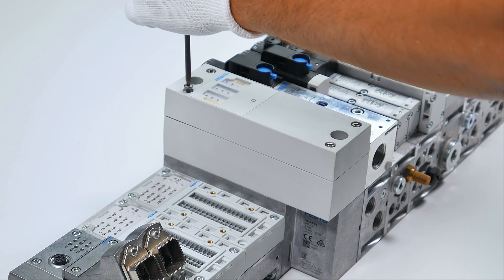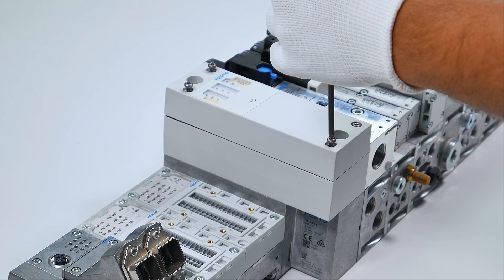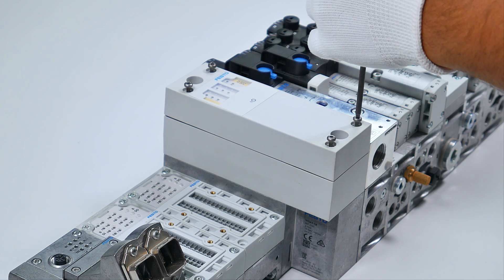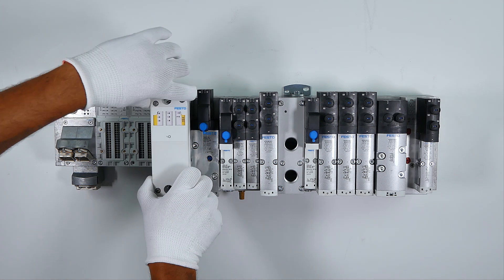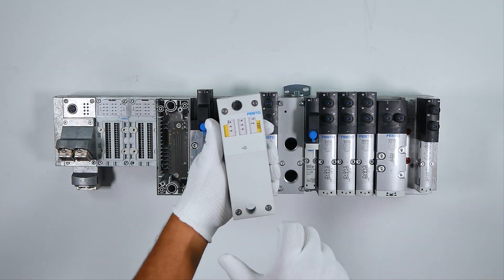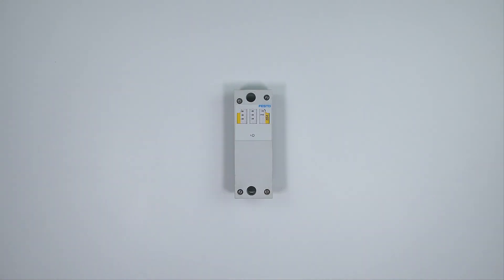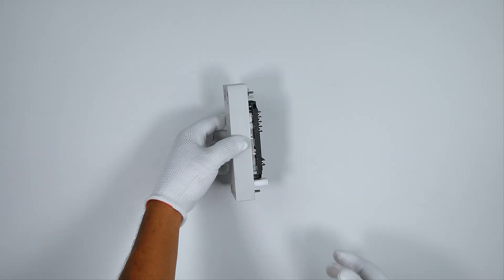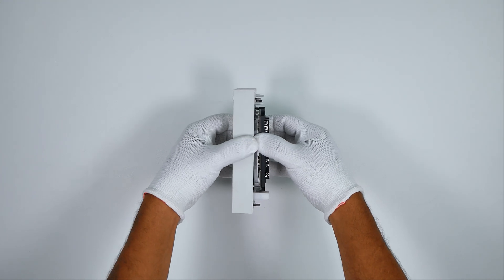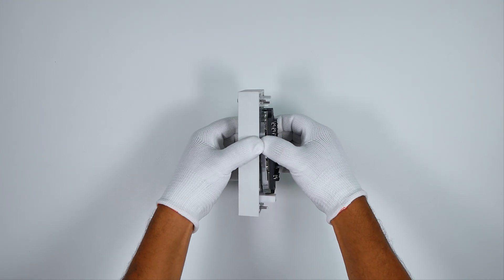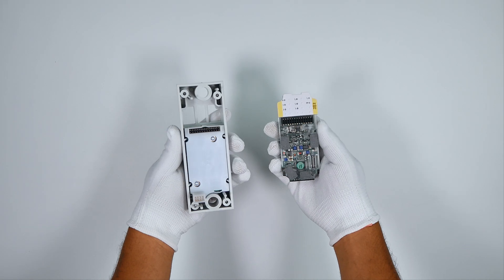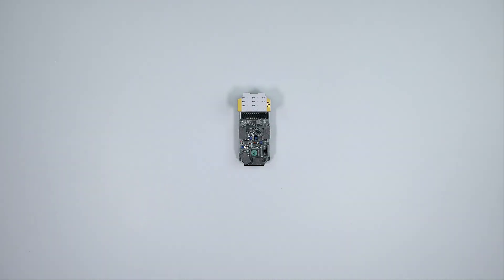Remove the top cover of the pneumatic interface module. Take out the safety module from top cover. Set the required ProfiSafe address using DIP switches. You can find the DIP switches on the bottom right corner of the safety module.